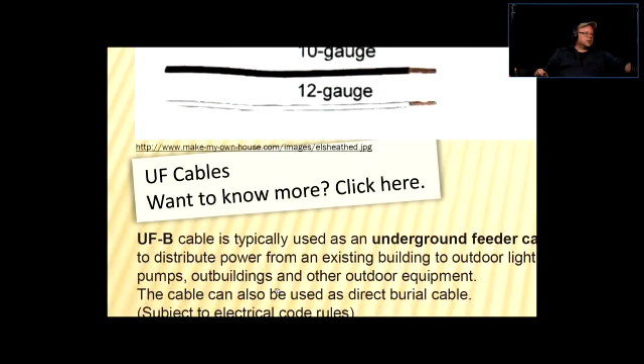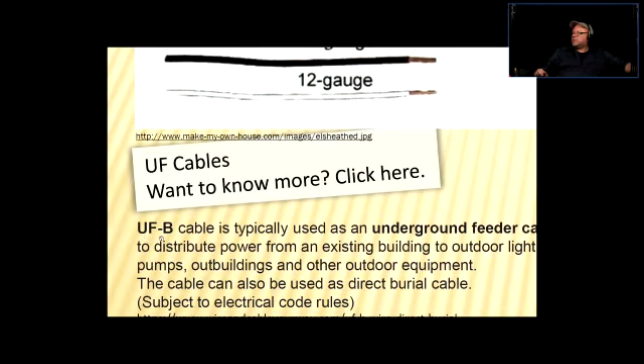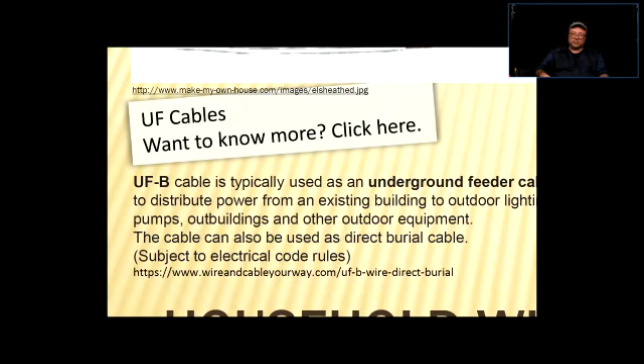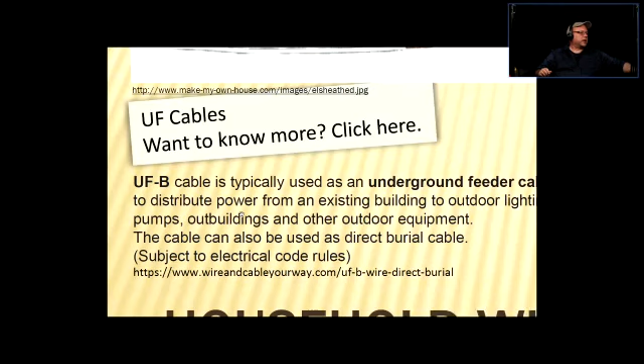It could also be labeled as UFB, underground feeder direct burial cable. Some cables can be used underground, but they have to be enclosed in something. Some cables are called direct burial cable, meaning they could just be put in the ground by itself. It's all subject to the rules and regulations set by the local electrical codes wherever you are, whether in Canada, the United States, or Europe. Always refer to the electrical code.